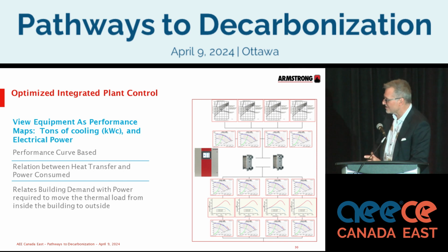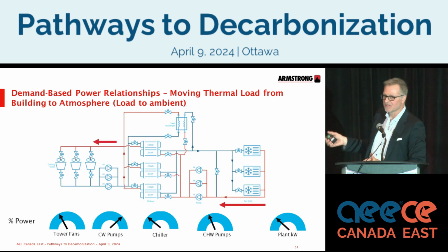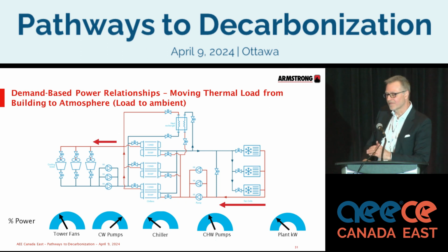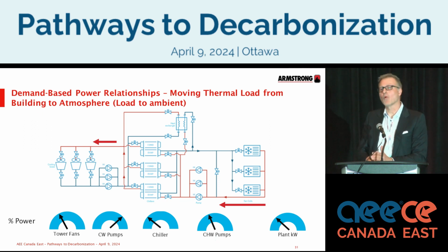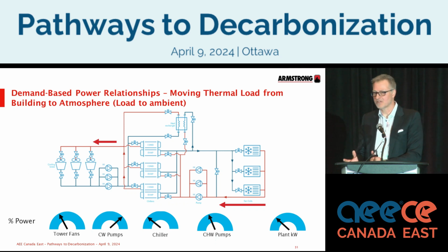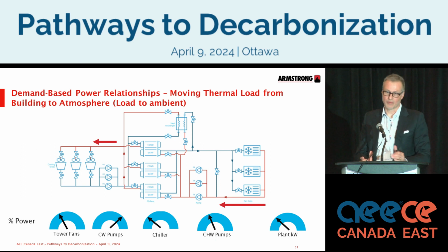What we do then is that if we're looking at each piece of equipment, we're trying to get down to the lowest kilowatt per ton. And a colleague of mine explained this in the most eloquent of ways. This logic here is almost based on supply and demand. So first of all, if I have to add 1 kilowatt more power to move a certain unit of thermal energy, where is it best to put it?